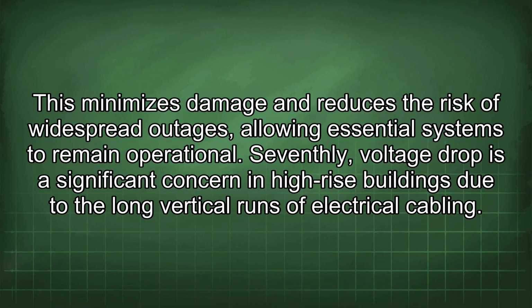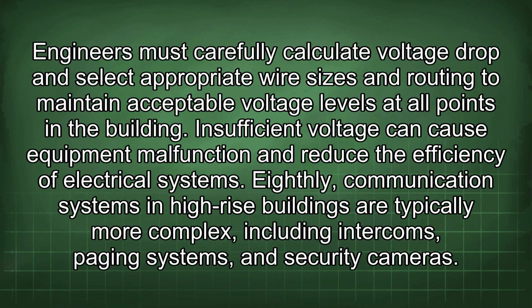Seventhly, voltage drop is a significant concern in high-rise buildings due to the long vertical runs of electrical cabling. Engineers must carefully calculate voltage drop and select appropriate wire sizes and routing to maintain acceptable voltage levels at all points in the building. Insufficient voltage can cause equipment malfunction and reduce the efficiency of electrical systems.